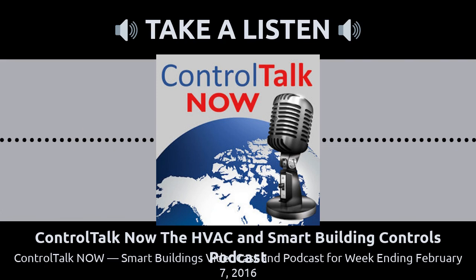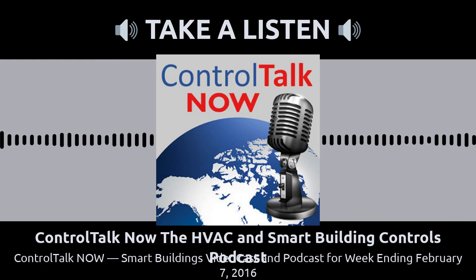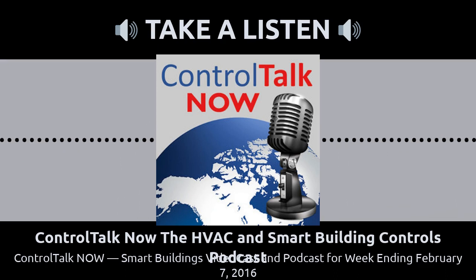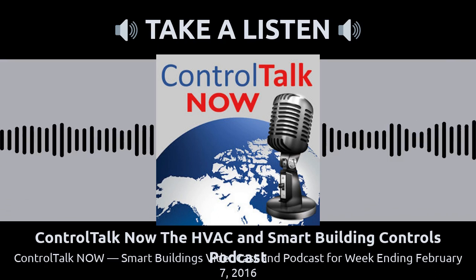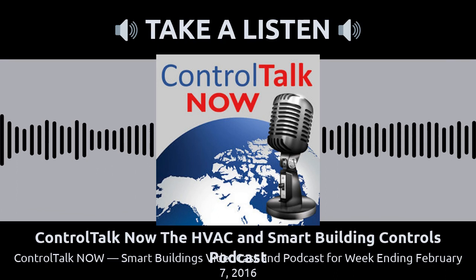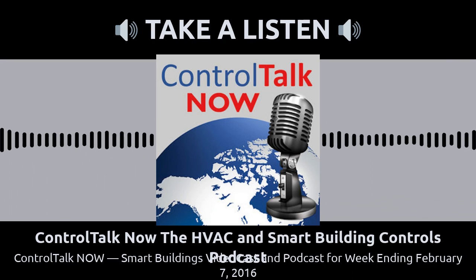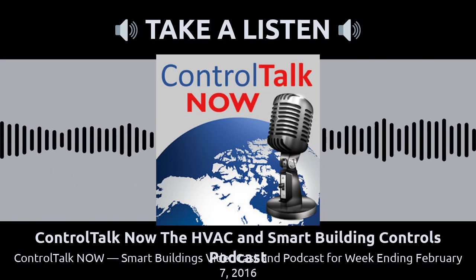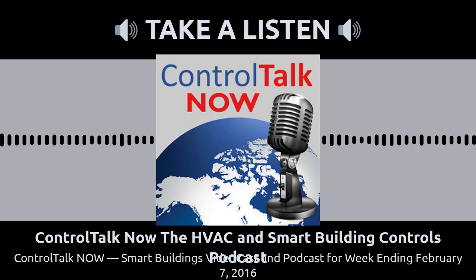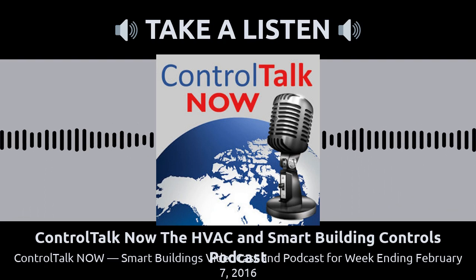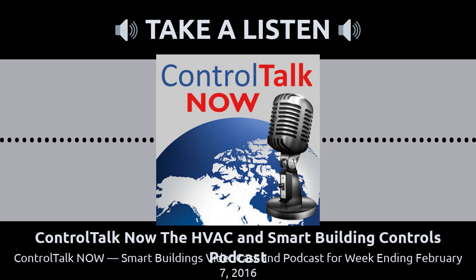So here's this control in one thermostat, and it's very competitively priced, and now it's available in BACnet so that you can network it. Again, the trick in our world in the light commercial building space, the race to the small space as you put it, is you've got to get fixed right away. You don't have time. So you put the thermostat on the wall, you've got the equipment under control, it's doing what it's supposed to do automatically, done, walk out the door. But then in the future, as the budget provides or as the needs dictate, you can now take that thermostat and immediately BACnet connect it to your system. So this gives you remote access, global scheduling, all kinds of fascinating operational savings. You get your energy efficiency and energy savings right up with the thermostat installation, and then you get your operational savings as the needs dictate.